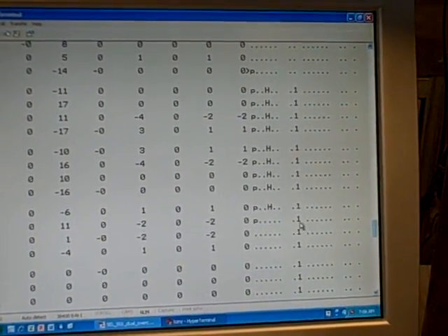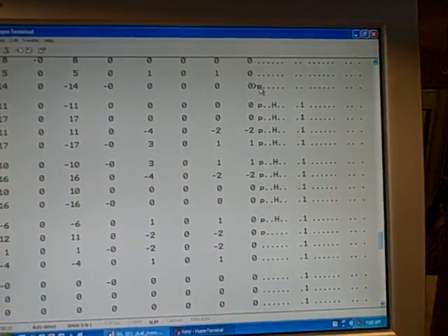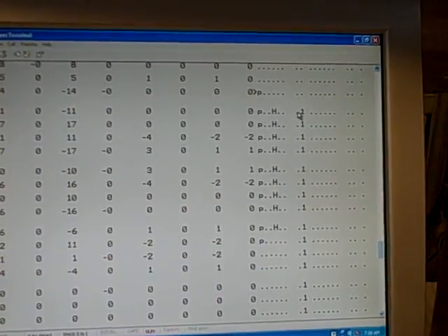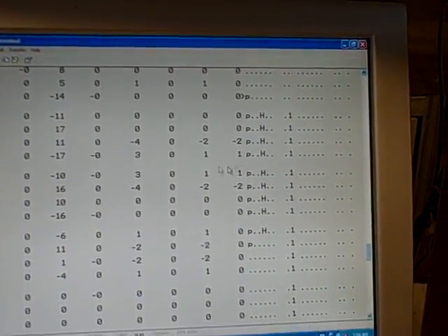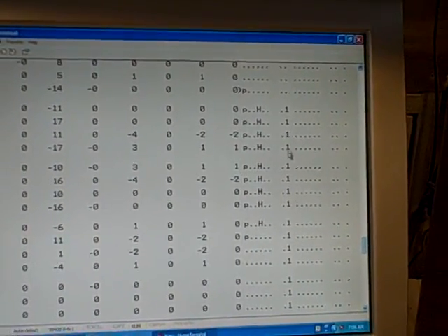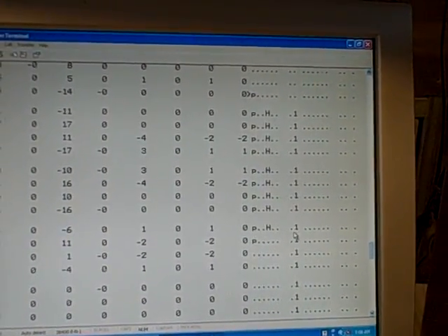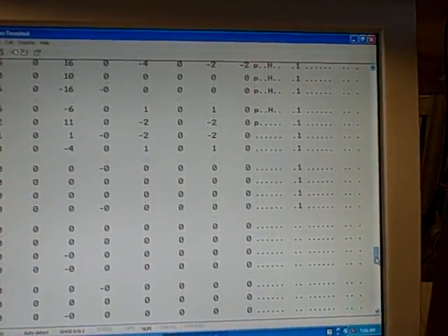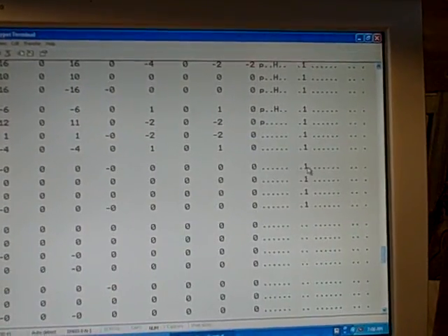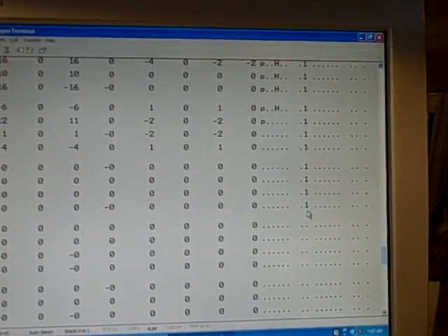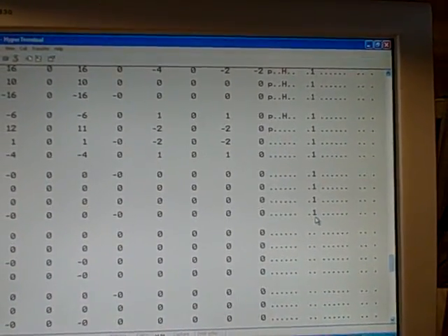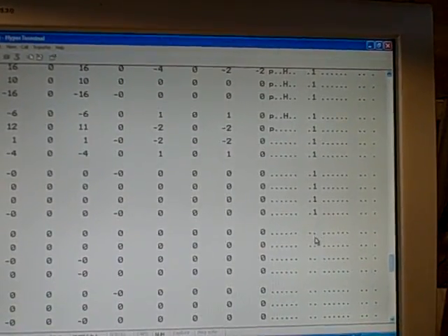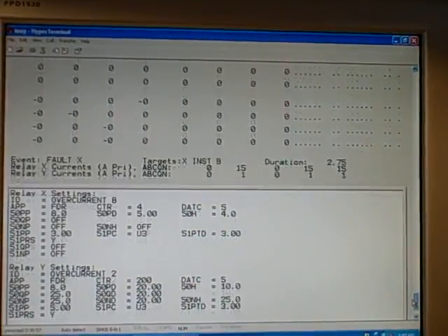This is very important diagnostic information. It tells us what element of the relay picked up, which is important when you have multiple elements at work. It also tells us when it asserts the output contact to trip the breaker, and diagnostically, we can tell from the data how long it took the circuit breaker to trip. In this case, a little over two cycles worth of time. Very valuable information. And then here, as you see, we're scrolling further down. At this point, it stops asserting the contact out to the circuit breaker. It's realized it's already tripped. There's no point in trying to trip it anymore, and so that bit goes to a zero state again. So that is our report summary.